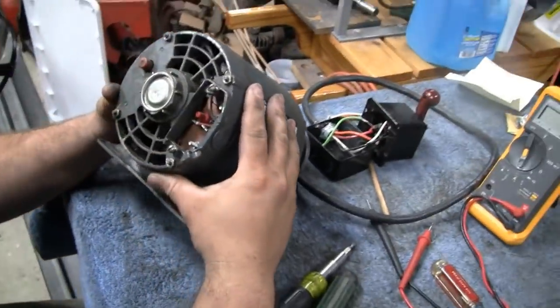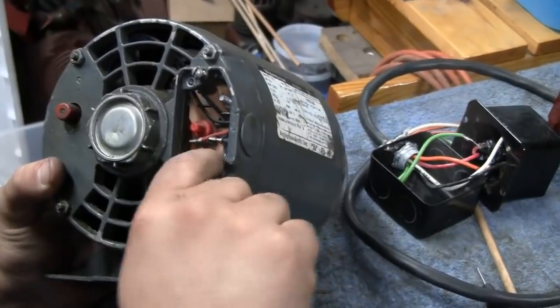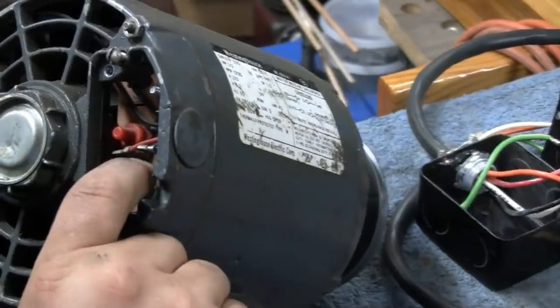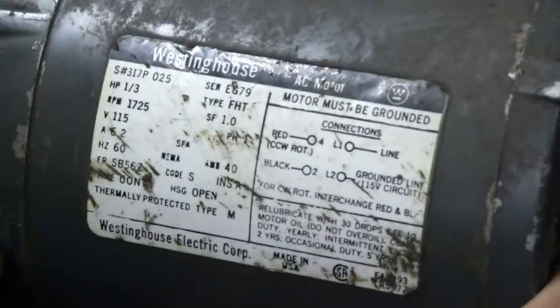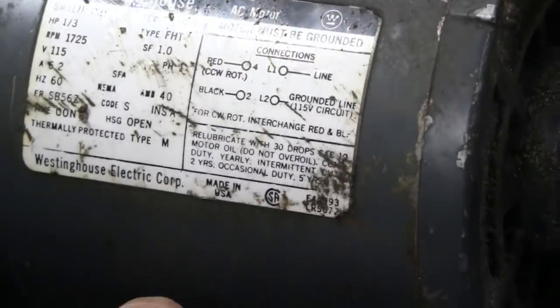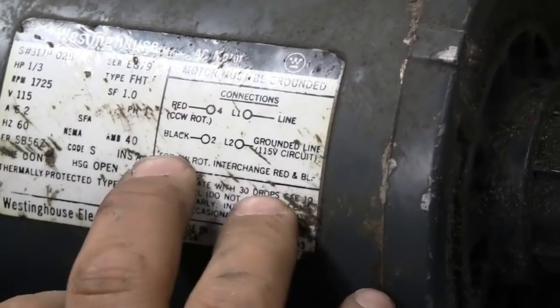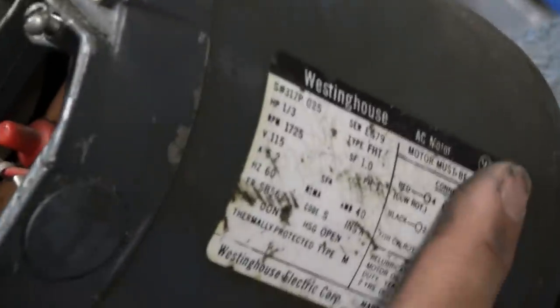Alright, here we go. There's your internal connections to the motor - L1 and L2, those are the lines. Typically you have to reverse two leads, so it looks like there's two and four there, and then there's one there. For counter-clockwise rotation, red and black on four and two. For clockwise, interchange red and black. So we just flip them around. Red and black on four and two.